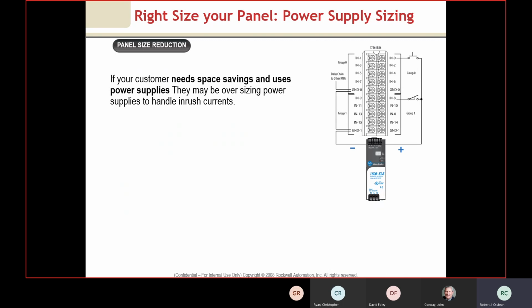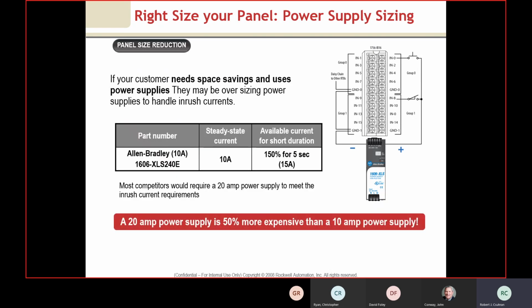So when we look at the power supply, typically what a customer will do is they'll oversize the power supply for the panel. That does a couple things. It increases the cost of the power supply typically, and it'll increase the size in the panel as well as the heat dissipation. In this discussion, we're talking about one of our efficiency power supplies. It's got a steady state current of 10 amps, but it has surge up to 150% for 5 seconds. That gets us to 15 amps.